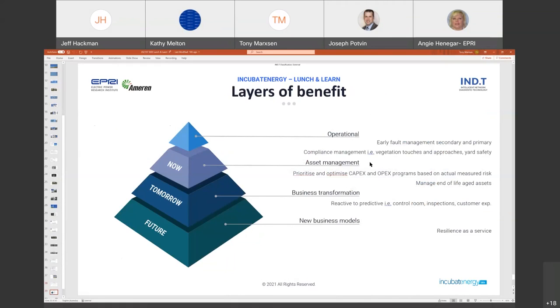IND Technologies' view is that right now, all the stuff we've talked about are operational benefits: compliance management for vegetation contractors, early fault detection that prevents outages and fire starts. Asset management is another area some customers are getting into, instead of a time-based, service-life-based approach to end of life, maybe the EFD data is a good guide as to when assets really need replacement. We see transformers, for instance, 98% of the ones on the distribution networks we monitor are absolutely fine, 2% are singing. They've been damaged, they've got excessive partial discharge, so maybe you just need to pay attention to those.